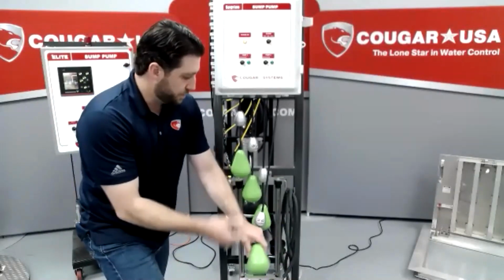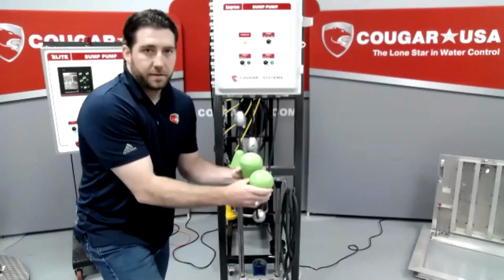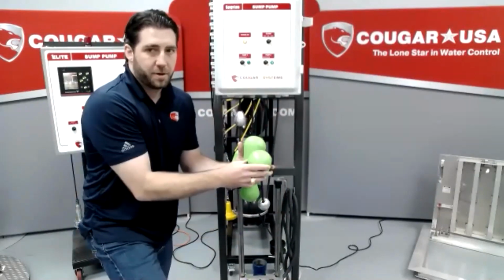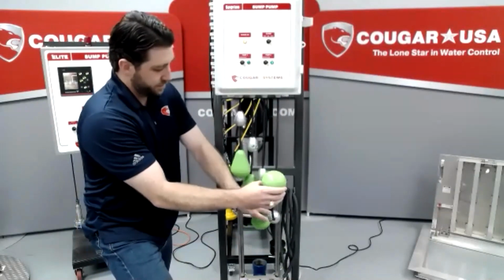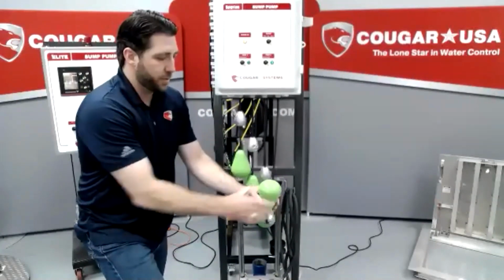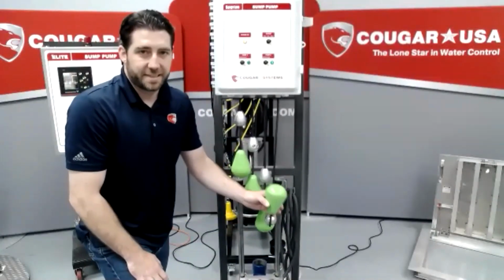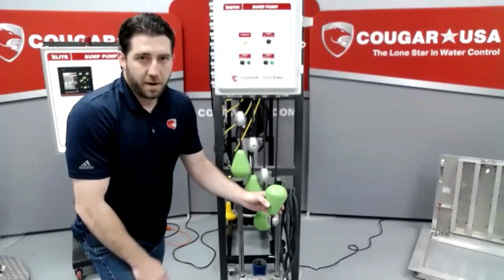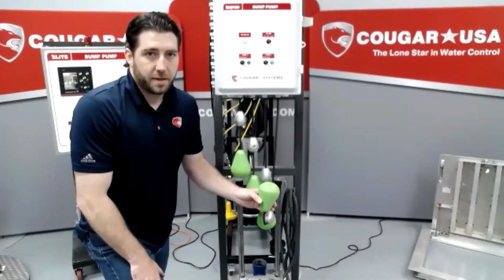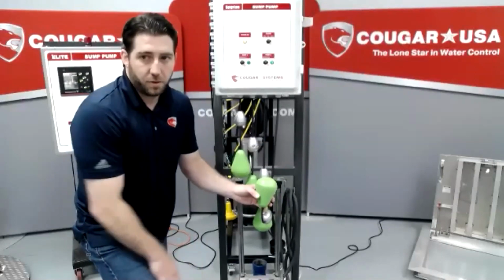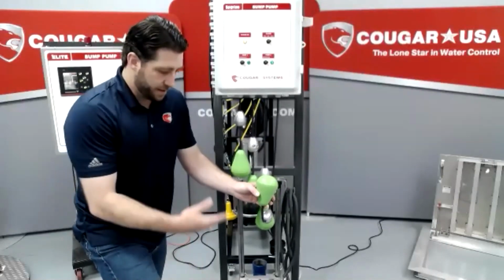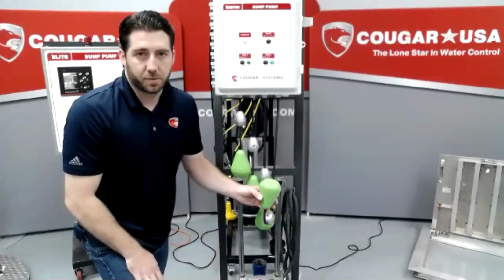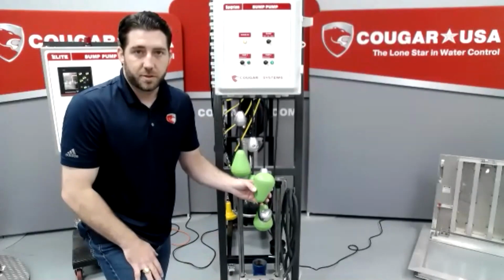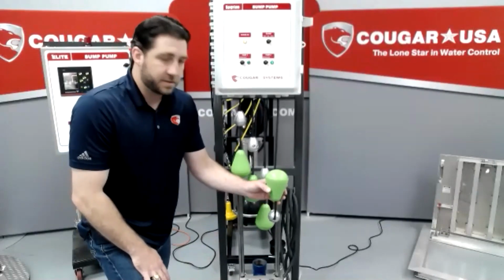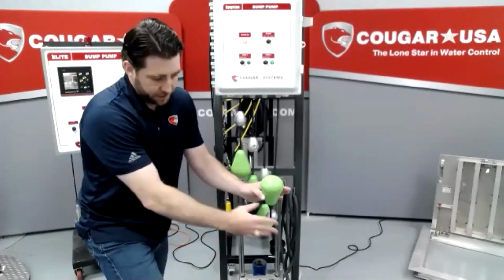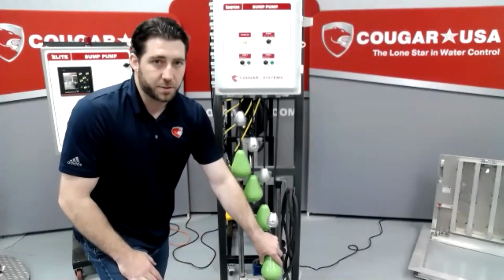Okay, so if we were to repeat that again, my pumps alternate every time. So my second pump came on, but if my lead pump on float goes down, but for whatever reason my pump off float gets stuck, these are going to stay on forever. The only thing that's going to turn it off is the thermal overload inside the motor. There's not anything within the controller that's going to stop this from running. So we address that on the Elite series with a maximum run timer. But on these, you've got to make sure that this bottom float switch is clear and free and is not going to get hung up, so that it can go down.